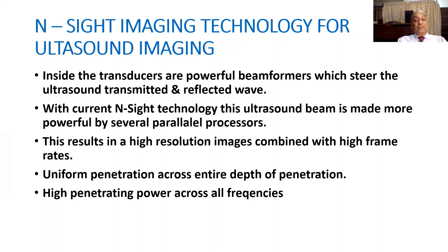Normally, if you use a high frequency probe, the penetrating depth is rather low. And if you use a low frequency probe, you lose the resolution to some extent, but you have a higher penetration. But with this technology, you have a penetration which is across the entire range of these frequencies, and the entire depth of this penetration is actually there. So this is what I have told you so far, that with these technologies, conventionally, the users had to choose between the frame rate and the image quality. But now with the N-Sight imaging, you can get a higher quality image with a higher frame rate.